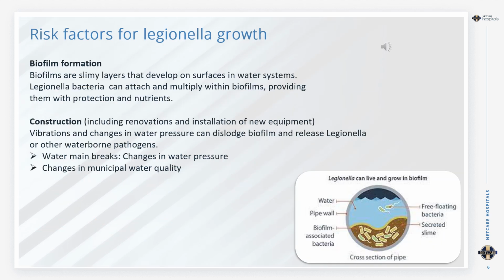The next risk factor that we will look at is biofilm formation. Biofilms are slimy layers that develop on surfaces in water systems. They are complex communities of microorganisms that stick together and adhere to surfaces. Legionella bacteria can attach and multiply within biofilms, providing them with protection and nutrients. The picture on the right-hand side of my slide is a cross-section of a pipe, and this shows you how Legionella can live and grow in biofilm.